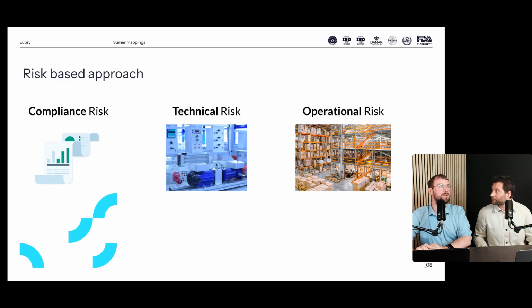Yeah, and often we would also see that for summer mapping specifically, technical risk can play a huge role because it could also be doors and gates and forklift chargers, any sort of technical installations that could impact the stability and the homogeneity of the space we're trying to map. So it's really a lot about seeing the infrastructure of the building or of a smaller temperature controlled unit, but really trying to emphasize the technical part versus the operational and compliance risk. And it shows really nicely to the auditor that you understand that there are different aspects to your risk assessment, that you're considering compliance, technical, and operational, as those are not often linked, but can be categorized differently, right?